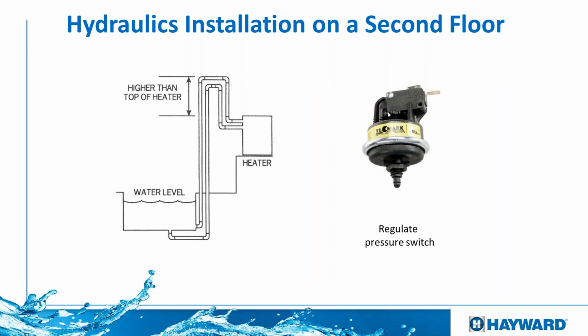So we want to make sure that we adjust it so when the pump is off, the heater will not come on, will not detect flow. And then when the pump comes on, the heater will fire. So we need to adjust this switch.